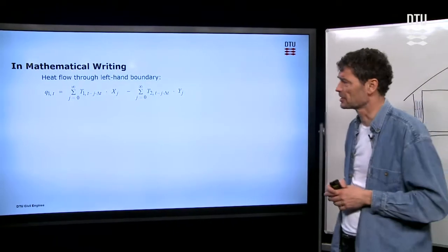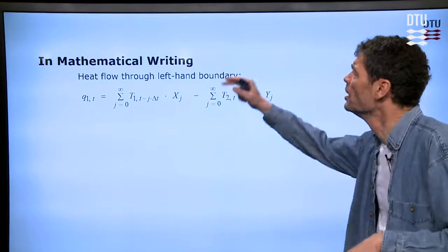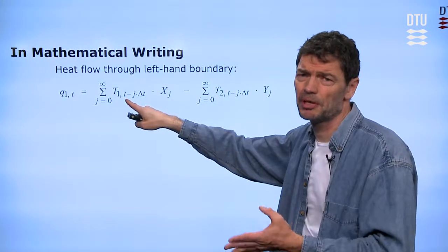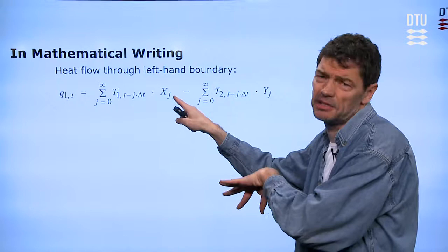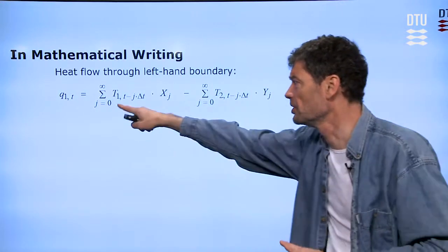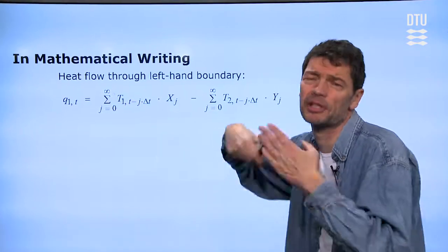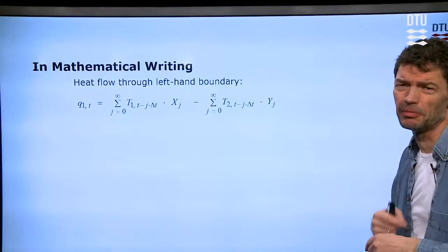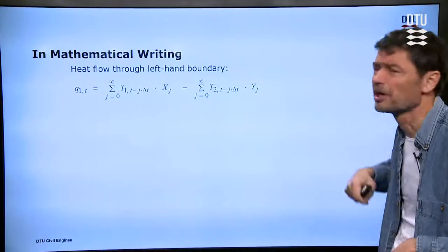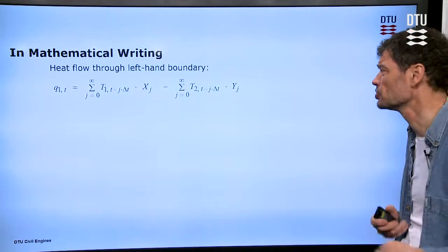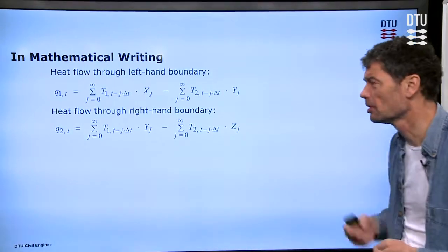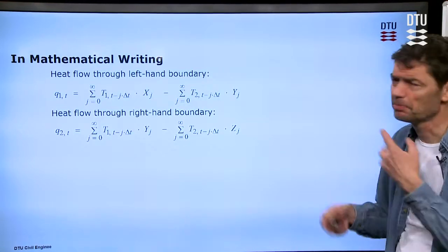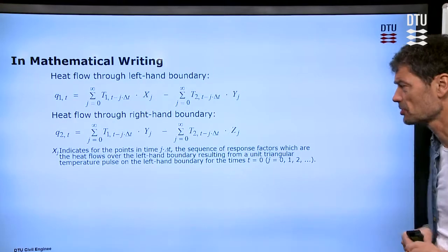We can write it all up mathematically. So, this will be my last slide. Here the heat fluxes, on one side, as a function of temperature, it's a summation of the temperature impulses that we had on one side times the X factors, that time series of X factors on that side. We add up infinity, in principle, but in reality only a certain few number of hours. And then we should subtract the impulse from the temperature on the other side of the wall, multiplied with the Y factors that are across the wall. And then we do the same for the other side of the wall, the right-hand side, in similar writing.